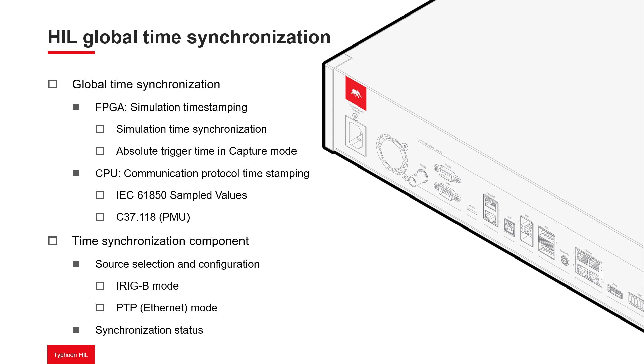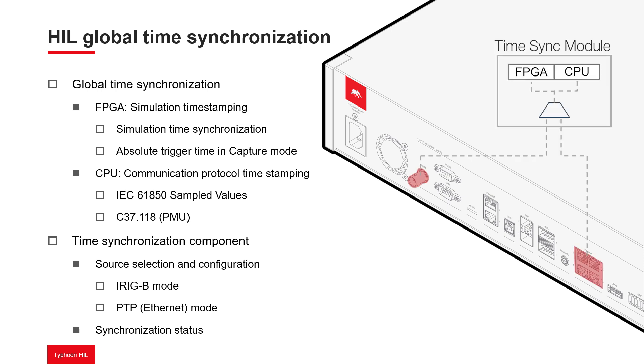There are two synchronization sources which can be utilized: IRIG-B and PTP. When IRIG-B or PTP is a time synchronization source, the exact time information is received every second, and the HIL time is updated constantly, ensuring that all network messages have the correct timestamp.